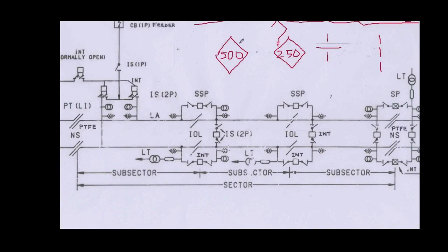So a locomotive driver who sees this board understands that after 500 meters, he has to trip the breaker because there is a neutral section. Here, this means after 250 meters, there is a neutral section. Here, he is supposed to trip the breaker. So this is the procedure followed by the loco pilot. However, accidentally, if he fails to do that, huge sparking would occur. And to identify that sparking and trip the breaker, panto flashover protection would be provided.